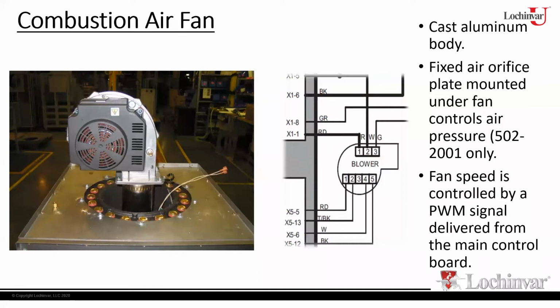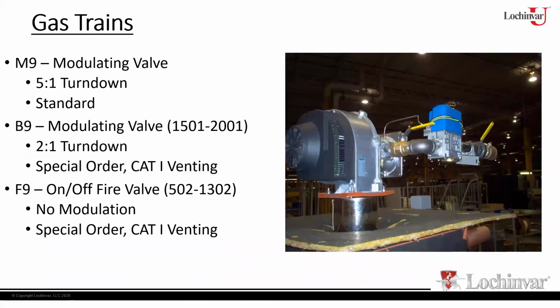So we got our blower. That's our main component, controlling the gas flowing from our gas train. So let's take a look at the gas train. This is the next item. You'll notice here I've listed three control numbers, M9, B9, and F9, and we'll delve into this as we look at the gas train. The first one there is M9. M9 is our standard gas train configuration. It's a 5-to-1 turn down, fully modulating.